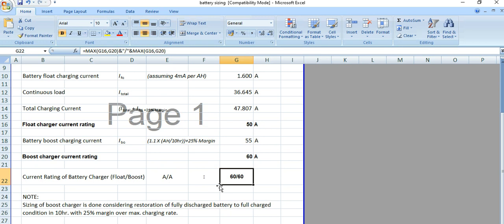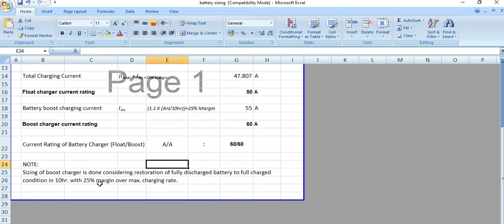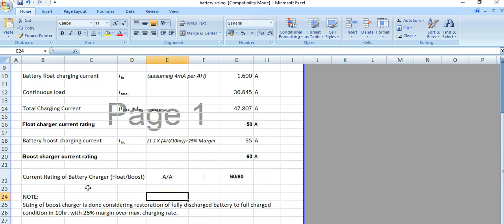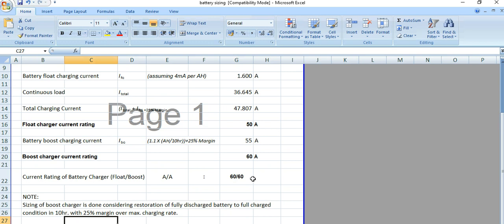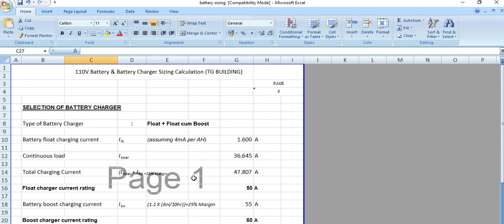You can note one important point here - the sizing of the boost charger is done considering the restoration of a fully discharged battery to full charge condition in 10 hours, because this is a C10 battery, with 25% margin over the maximum charging rate. This is the battery charger selection: 60 ampere for both float and boost charger.